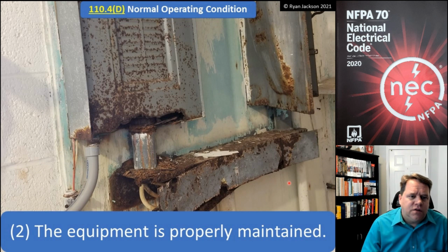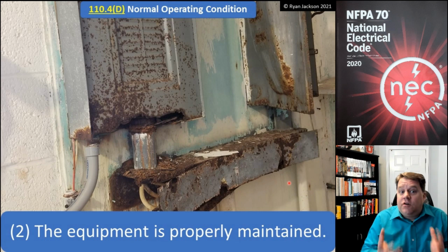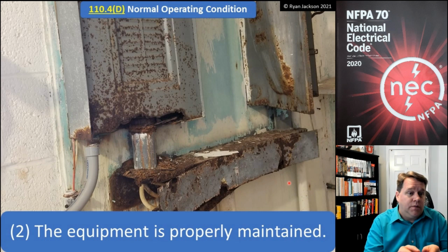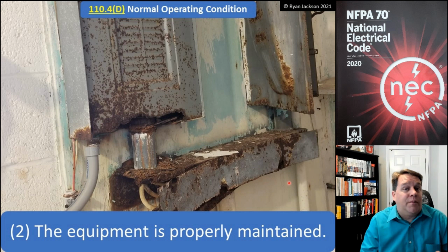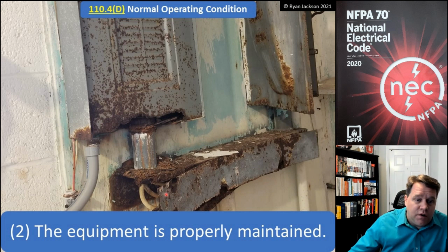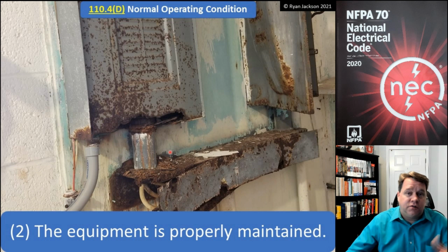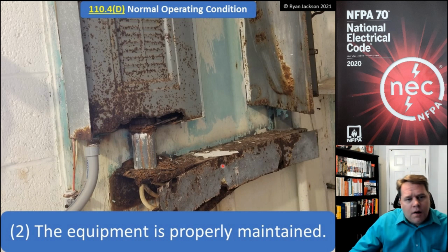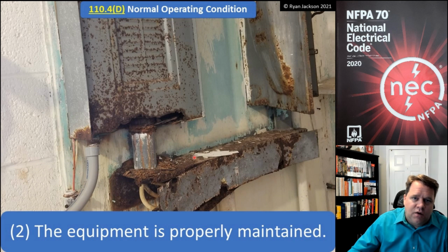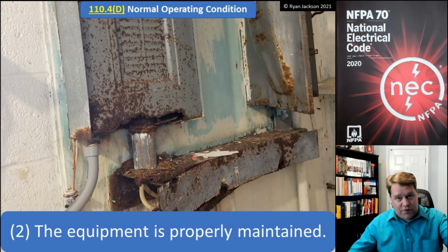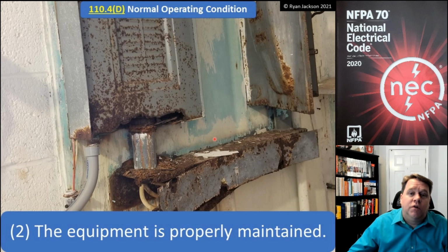Can I go into this room and start flipping circuit breakers? No, there is no normal operation of this equipment because this equipment is not in a normal operating condition. If the equipment is falling apart due to corrosion, this was actually at a swimming pool equipment room, which makes this even more frightening. Can I walk in there and turn on and off the circuit breakers? Absolutely not. We don't know what the inside of that panel board is like. We have no idea what might happen when we start turning breakers on and off. There's a very real chance that we end up having an arc flash in that piece of equipment.